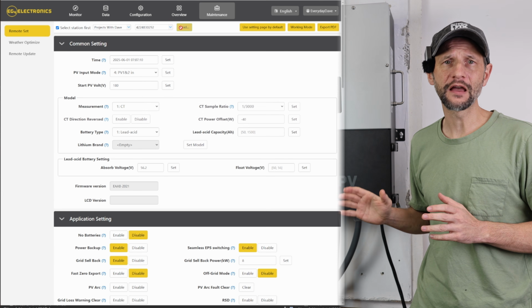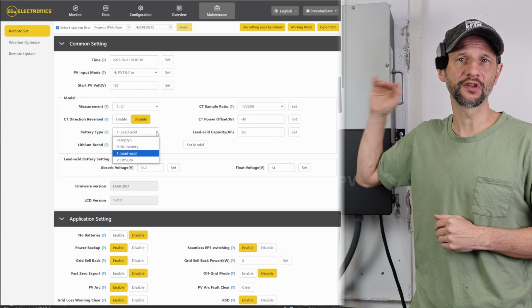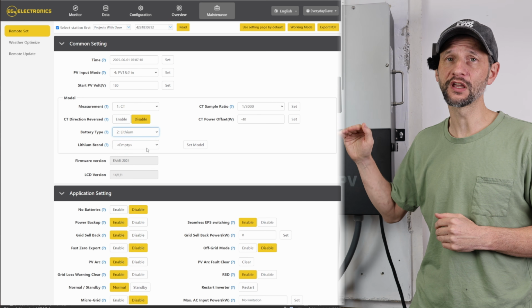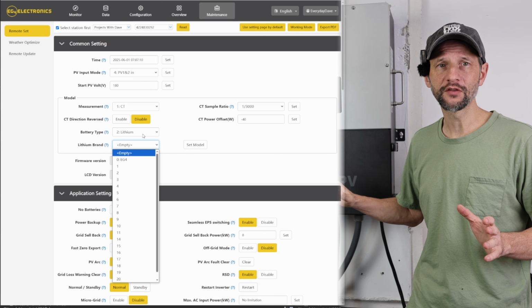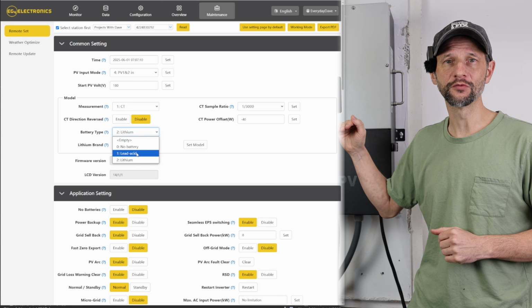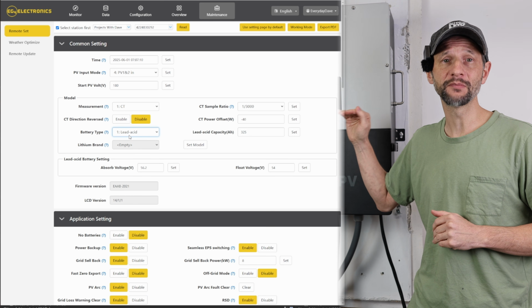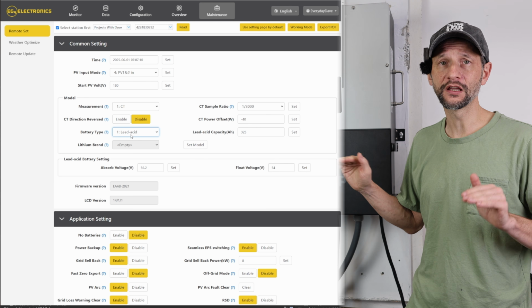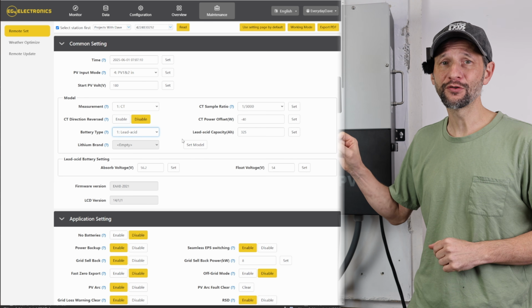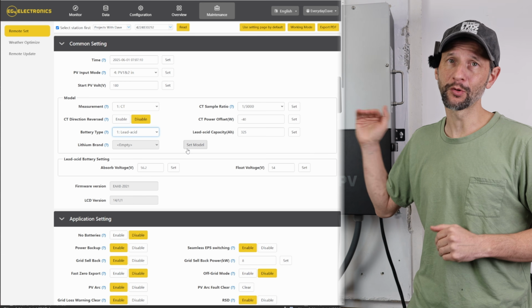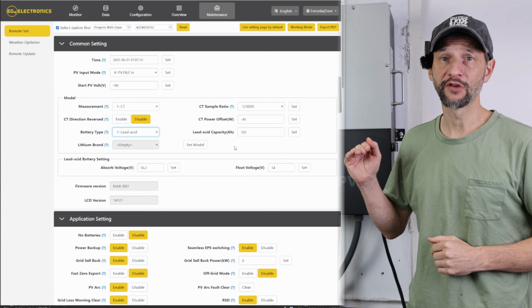If I were installing a battery with established communication, I would select lithium and the corresponding communication protocol. For any other lithium iron phosphate battery, I can use the user mode. It's labeled lead acid in the setup menu, but you can use it for any custom profile. When you click Set Model, the inverter will restart, so be prepared for that. This is a good time to talk about voltage settings.